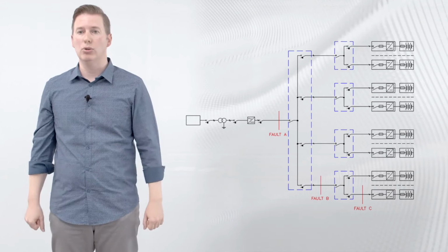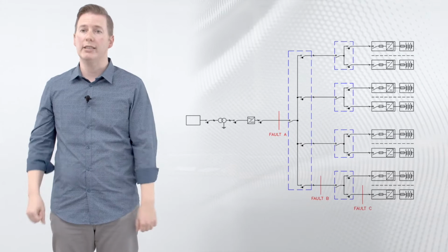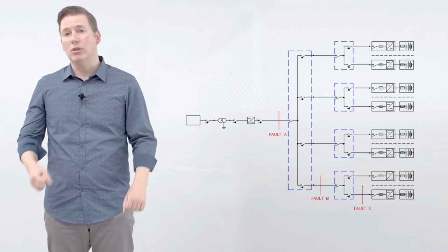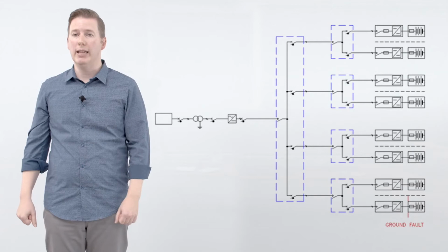It is important to know the maximum short circuit current in order to choose the circuit breaker with the right breaking capacity. Instead, considering the ground fault event, the main locations where a fault can occur is directly on board the electric vehicle or at the DC charger level through their so-called exposed conductive part. From the current contribution point of view, the two locations are practically equal, so we can just consider the first one. Like in short circuit event, also in this case, we have to know the maximum value of ground fault current in order to choose the circuit breaker with the right breaking capacity.